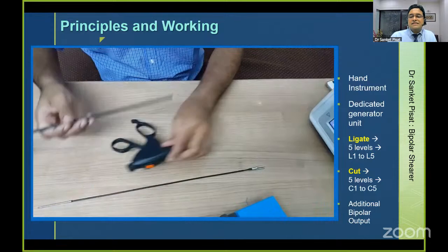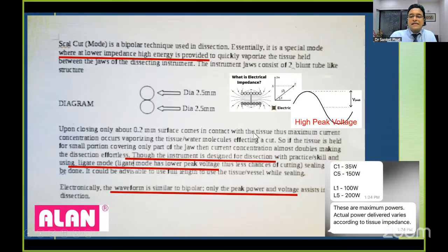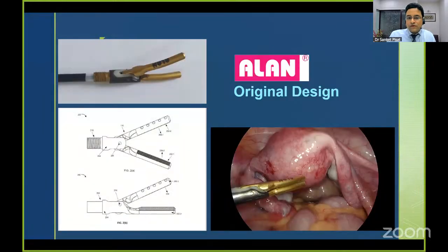However, how is this concept being used in bipolar? Generally, if you use bipolar coagulation, the tissue will slowly get coagulated until it dries up, resulting in sealing the tissue. Where the shearer differs from the rest of the technology available is that at a lower impedance, the unit is able to provide high energy. It is able to provide a high peak voltage at a lower impedance. So even when the resistance of the tissue is less, the current thrown inside is more, and therefore, using bipolar technology itself, the machine is able to cut and coagulate using the same settings, using the same design.